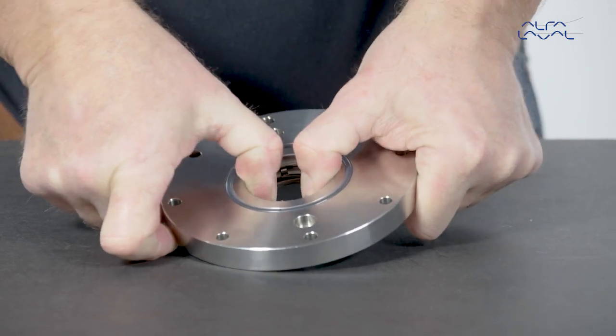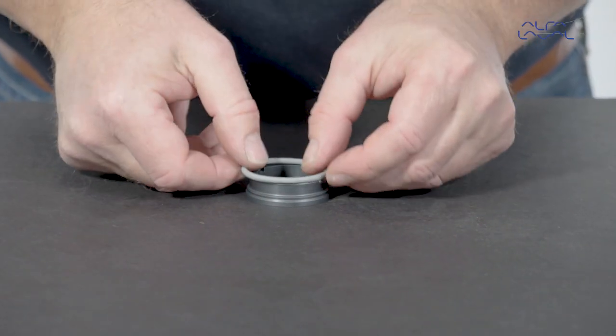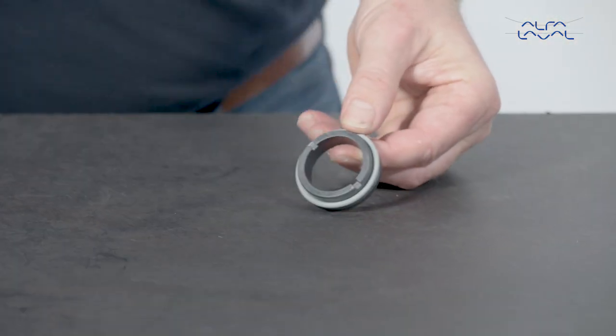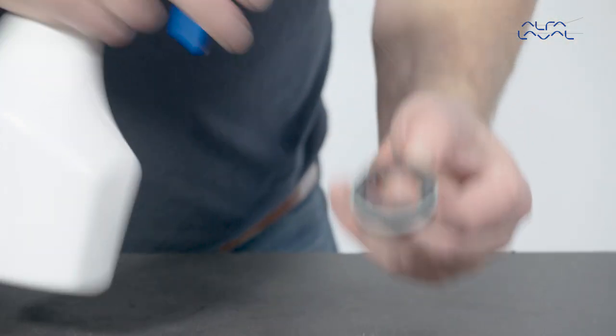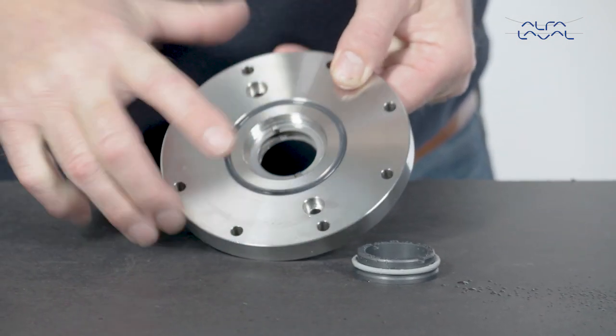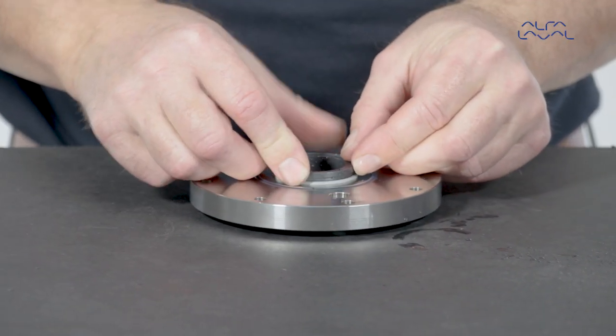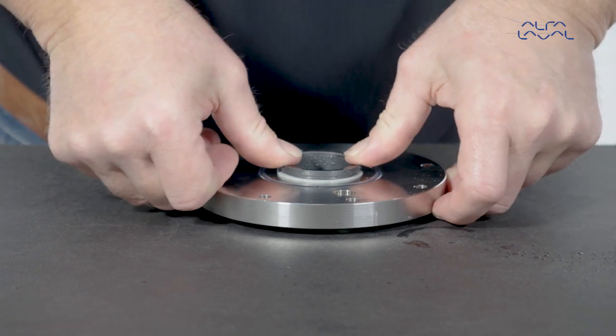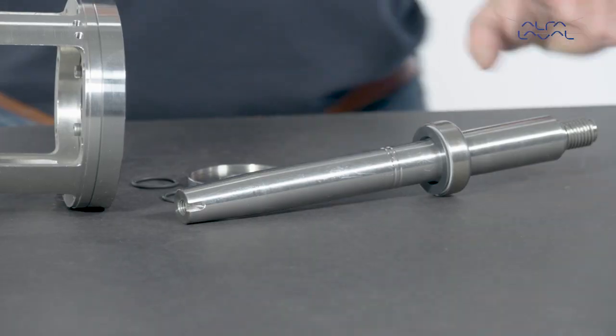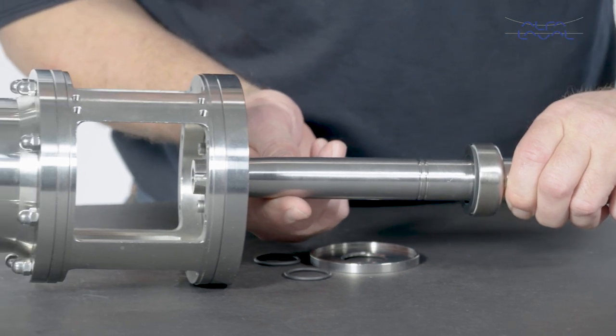Check the tension of the spring ring. Now place the O-ring on the stationary seal part and lubricate with water. Then place the stationary seal part on the flange. Check that the tabs of the drive ring are properly positioned. Gently press the stationary seal part into place in the flange.